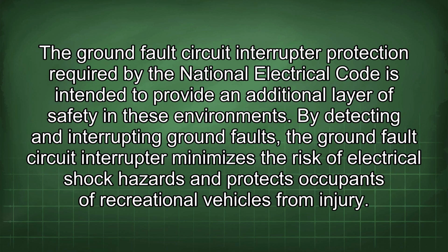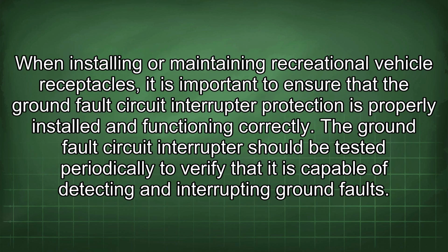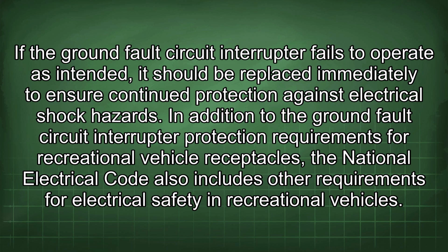The ground fault circuit interrupter protection required by the National Electrical Code is intended to provide an additional layer of safety in these environments. By detecting and interrupting ground faults, the ground fault circuit interrupter minimizes the risk of electrical shock hazards and protects occupants of recreational vehicles from injury. When installing or maintaining recreational vehicle receptacles, it is important to ensure that the ground fault circuit interrupter protection is properly installed and functioning correctly. The ground fault circuit interrupter should be tested periodically to verify that it is capable of detecting and interrupting ground faults. If the ground fault circuit interrupter fails to operate as intended, it should be replaced immediately to ensure continued protection against electrical shock hazard.